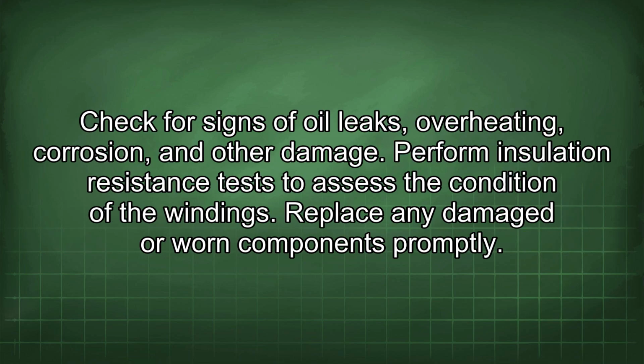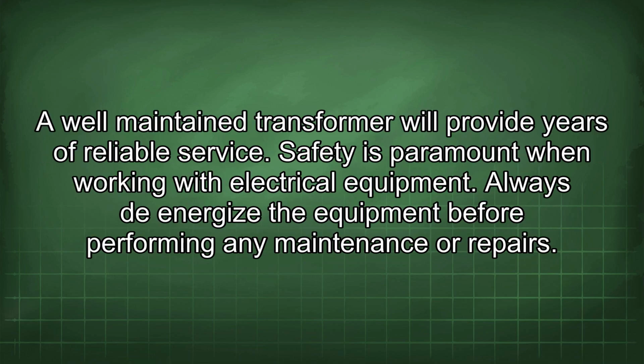Check for signs of oil leaks, overheating, corrosion, and other damage. Perform insulation resistance tests to assess the condition of the windings. Replace any damaged or worn components promptly. A well-maintained transformer will provide years of reliable service.